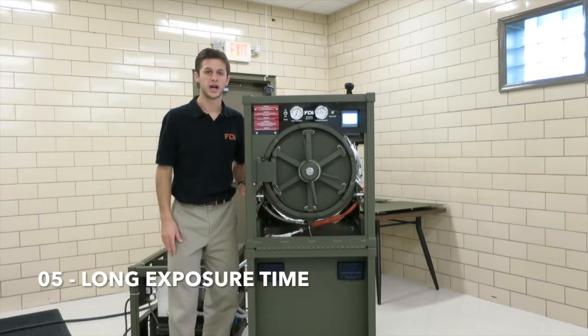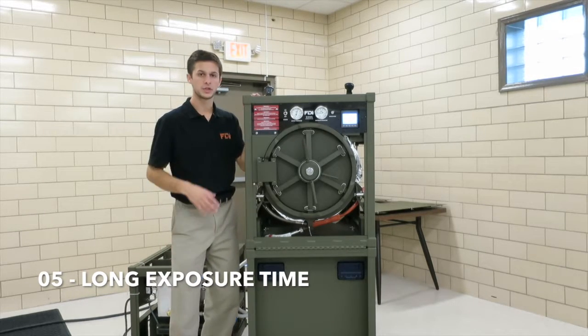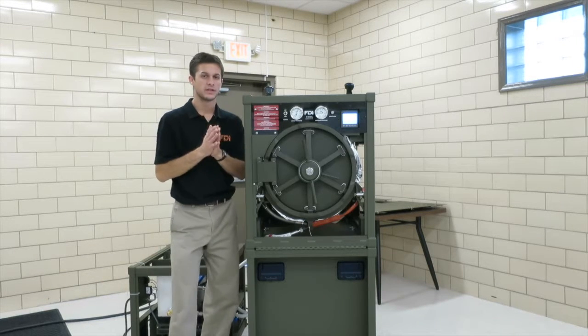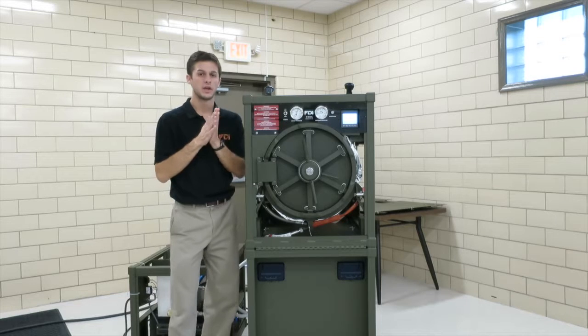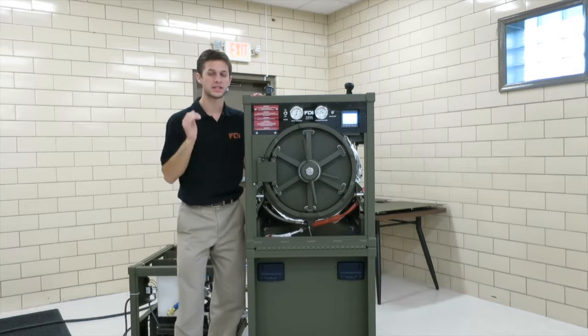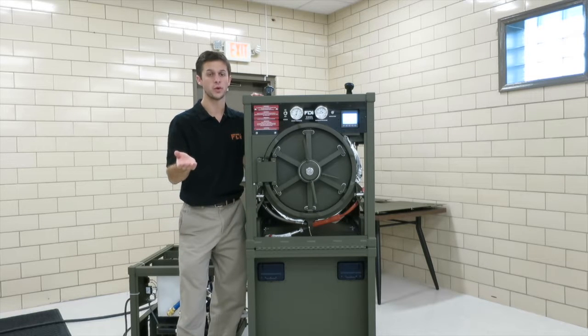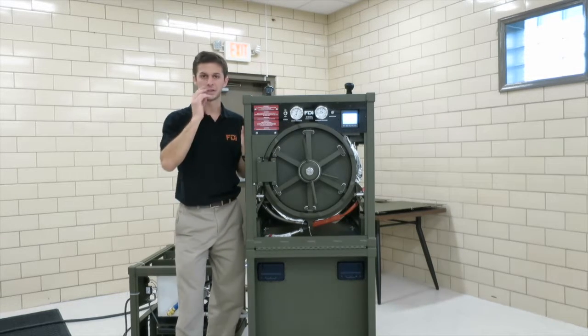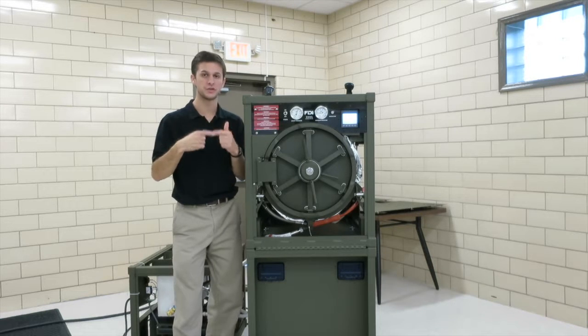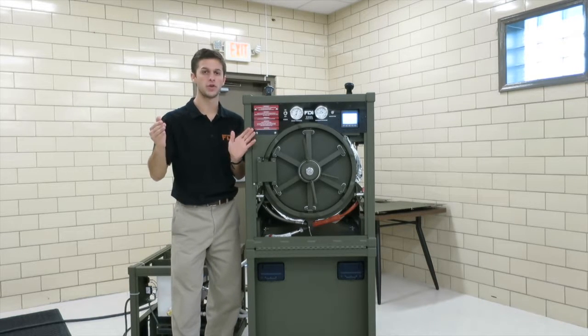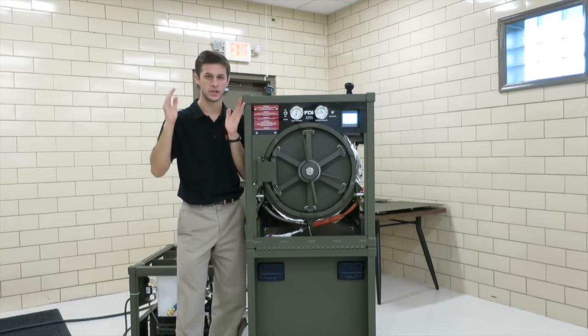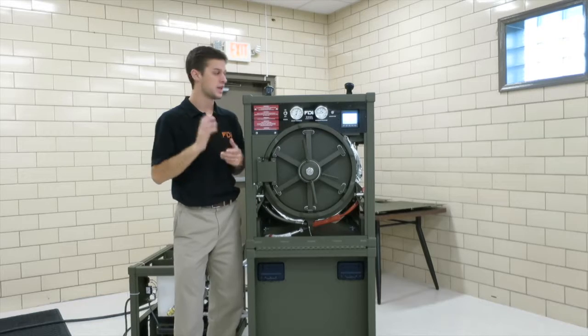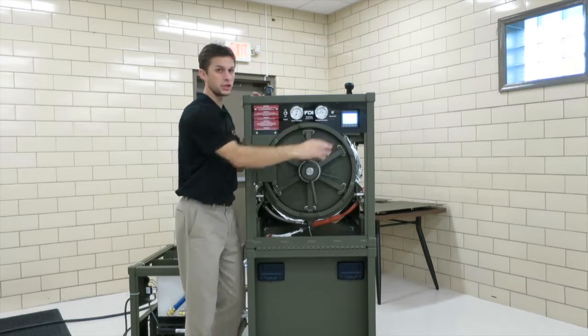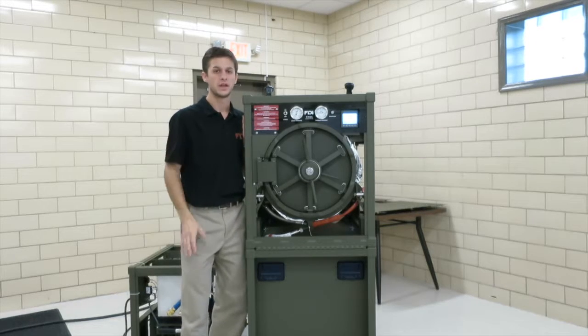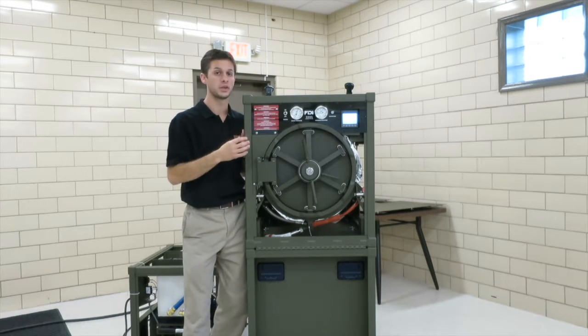Number 5 is long exposure time. This alarm is for when you're in a cycle and you're in exposure, where there's a certain amount of time that should be taken. Whenever the sterilizer is stabilizing and trying to find its set point of 273 degrees, or 274 for the Bowie-Dick, if it can't hold that and the temperature dips below, it'll go back into stabilization. If it does this a few times, the exposure is going to take longer than normal. Again, there's a watchdog timer that says it should take this amount of time to get through exposure. If it's taking longer, we're going to throw this 05 long exposure time alarm, because the PLC knows that it's not behaving normally.